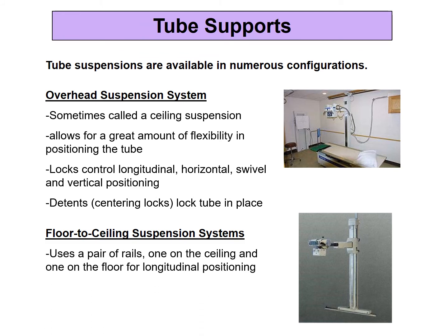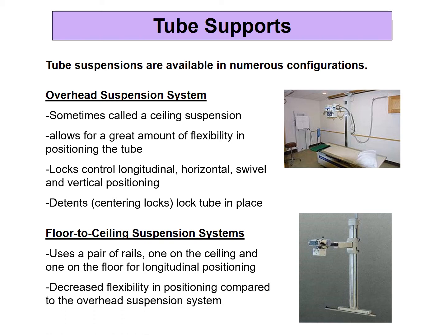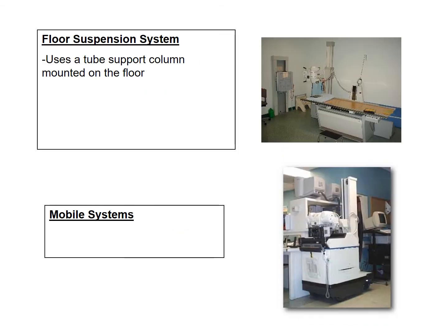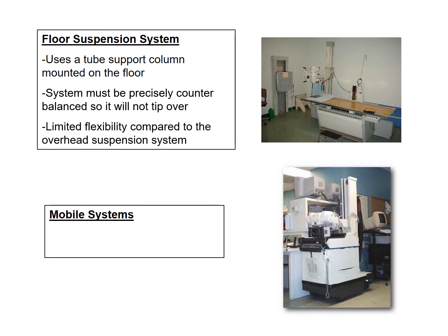As far as a floor to ceiling suspension system, it uses a pair of rails, one on the ceiling and then one on the floor for longitudinal positioning. You can see a picture of that over on the right. It does have decreased flexibility in positioning compared to the overhead suspension systems. There are floor suspension systems. These use a tube support column that's mounted on the floor. The system has to be very precisely counterbalanced so that it won't tip over, since it's not attached to the ceiling. Very limited flexibility compared to the overhead suspension system.